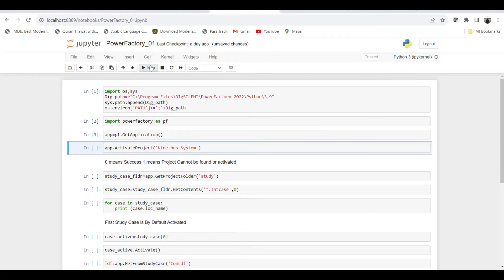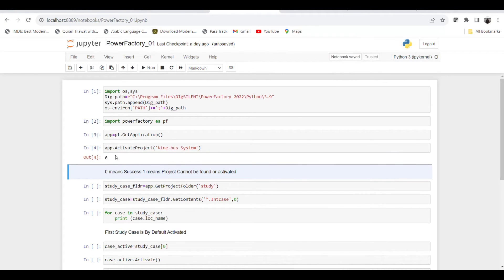Then we need to define which case to open. For this demonstration we are using a nine-bus system which is readily available in the PowerFactory examples. We use 'app.ActivateProject('Nine Bus System')'. After running this, you will get a response from PowerFactory — if the response is zero, the case has been loaded successfully; if you get one, the project cannot be activated and you need to figure out the issue. Once we press run, we receive zero, meaning the nine-bus system has been loaded successfully.